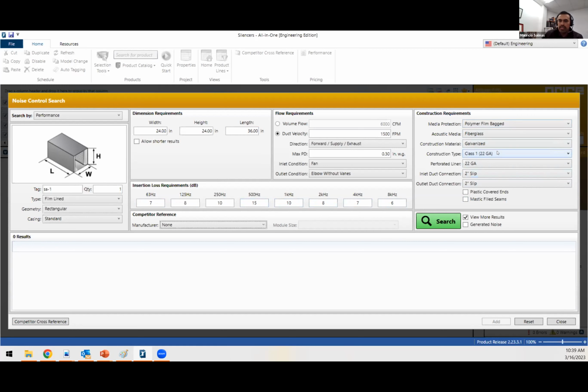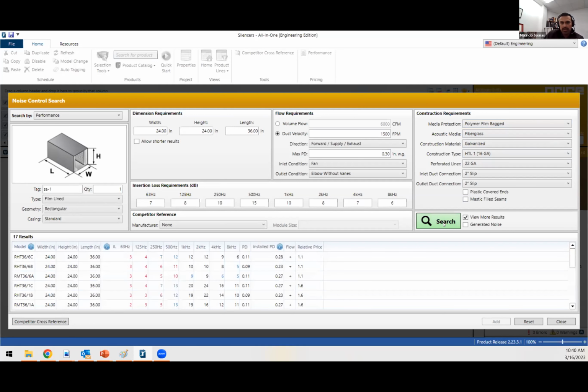You have a good sealing in place, so you don't have to worry about breakout noise through the casing. If all of a sudden your silencer is right above a critical space, think conservation of energy. A lot of the sound is going to want to come out from the casing, radiated noise. So if that's the case, maybe beef up your casing. Now, once you have that, you click search, and it's going to start searching for all the possibilities, all the different models that meet that performance.